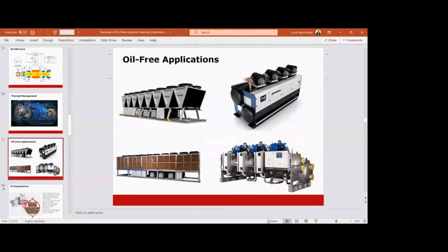So some of the common applications we do with oil-free are air-cooled application, water-cooled application, and evaporative condensing application. Evaporative condenser doesn't add any value in Singapore, but in some of the drier climates, evaporative condensing chillers do create very big value. 98% of oil-free applications are flooded vessels. So there's very, very little DX or direct expansion work in the field with oil-free compressors.